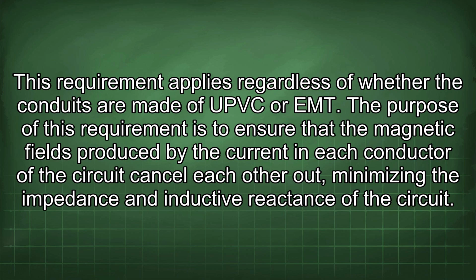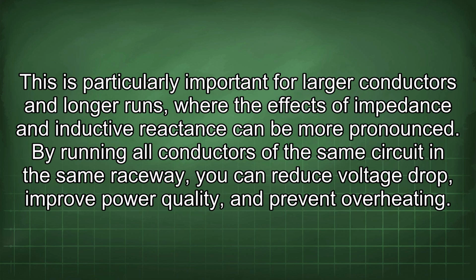The purpose of this requirement is to ensure that the magnetic fields produced by the current in each conductor of the circuit cancel each other out, minimizing the impedance and inductive reactance of the circuit. This is particularly important for larger conductors and longer runs, where the effects of impedance and inductive reactance can be more pronounced. By running all conductors of the same circuit in the same raceway, you can reduce voltage drop, improve power quality, and prevent overheating.